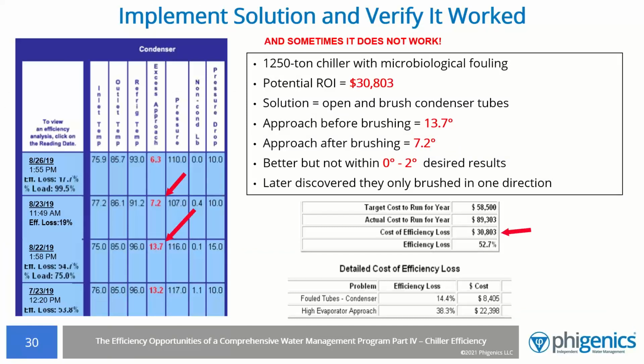The next step is to implement the solution to the problem. In this case, the indicated solution was to open the condenser and brush the tubes. This is not an inexpensive task, but as you can see, the potential ROI was over $30,000. The approach before the brushing was 13.7 degrees, and the approach after brushing was 7.2 degrees. A marked improvement, but the desired result was less than 2 degrees.